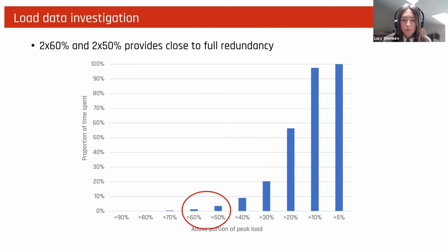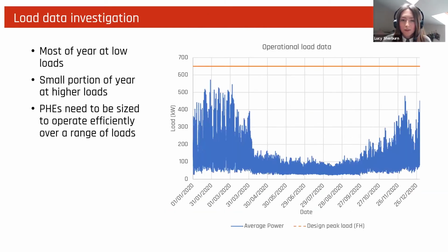So if we take a look at load data, yeah, that one, perfect. We can see why this is the case. This is operational load data from a site across the year of 2020. The design peak load can be seen by the orange line at the top. Then you can see the power across the scheme. We can see that for large portions of the year, you're operating at quite low loads, and you are getting close to peak load during winter, but not necessarily hitting that. So the takeaway from this is that your plates really need to be sized to operate efficiently over a range of loads.